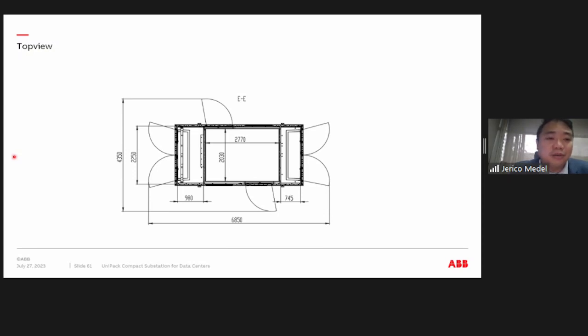It will still be the same CT-PT that we have used in a typical medium voltage switchgear. The only difference, as discussed with Sir Jaime, is that we are using an SF6 gas insulated switchgear and not an AIS, but both also use CT and PTs. So whether it's donut type or bar type CT PT, we can also accommodate. If there are specific requirements, we can comply with that, no issue. Kahit multi-core pa siya, yes, kahit multi-core pa siya, sir, yes.